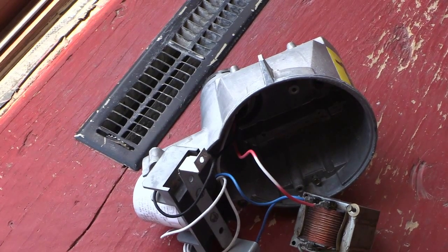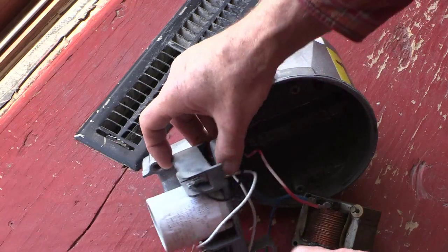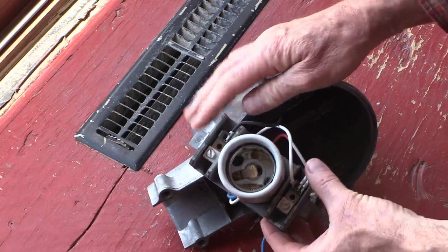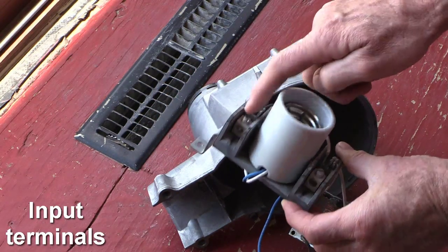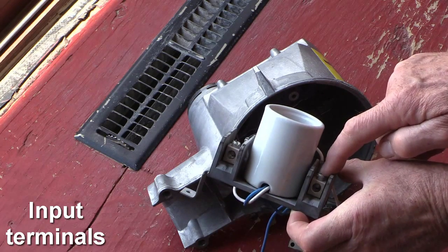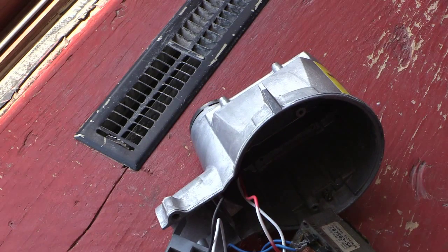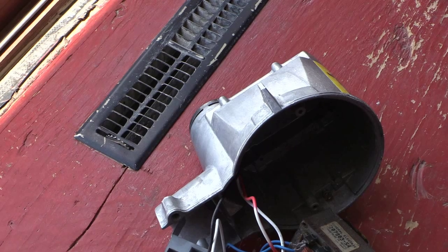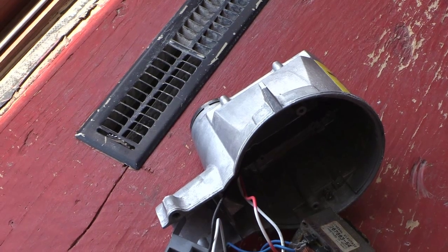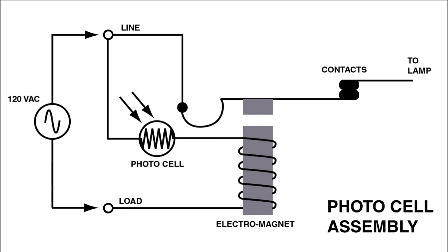If you have voltage to these two terminals and the light doesn't come on, first, most obvious, put in a known good bulb. Then generally you try a new photocell, but keep in mind that photocells generally fail with the light on all the time, because when the photocell works, the light causes a decrease in resistance through the photocell and the current flow creates a magnetic field that pulls the switch open.